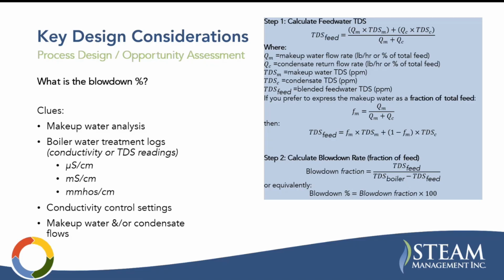So if you look at the equation here, this is solids in your feed water. Again, your feed water is the water coming from the deaerator to the boiler. So it's a mix of your makeup water and your condensate return. So in order to calculate blowdown percentage, you need some combination of these variables, which are makeup water flow, makeup water TDS levels, condensate flow, condensate TDS levels, or you might possibly have your TDS levels in your feed water in your water treatment log. So it depends where they're taking samples at. It depends what information you have.